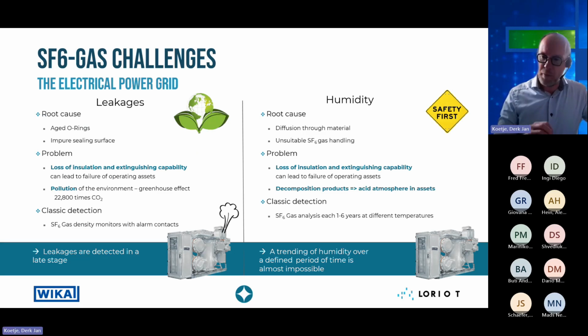What are today the two main challenges or main drivers when it comes to SF6 gas? The first one is leakages. The root causes of these leakages are aging of the O-rings, aging of the sealings, and impure sealing surfaces. And the problem is, as soon as there is a leakage of SF6 gas, it will stay in our atmosphere for more than 3,000 years. And when you look at sustainability and the reduction of CO2, we need to keep in mind that the global warming potential of SF6 gas is 23,000 times higher than CO2. So every loss of SF6 gas will have a huge impact on our environment.